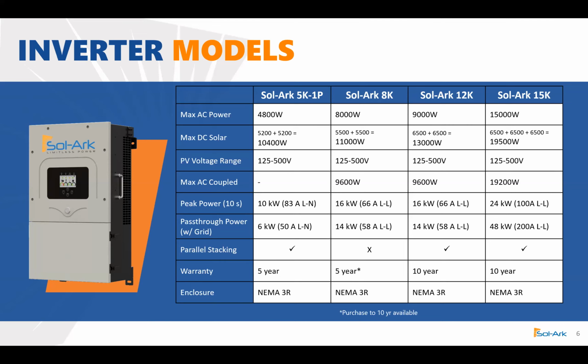And the Sol-Ark 12 and 15K come standard with a 10-year warranty. They also come with the NEMA 3R enclosure. That means you can mount it outside in the rain and dust, and it's going to be fine. There's no exposed electronics on the inverter. It just has some ventilation in the back that exposes the heat sinks, but you can run a hose through it and it'll still continue to work.